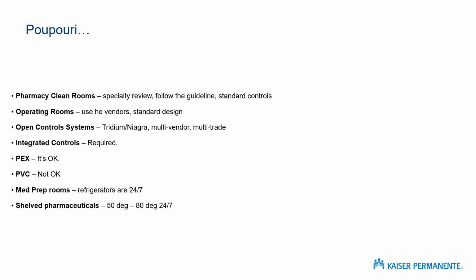Operating rooms, again, we have some standard vendors. We have memorandums of understanding with 2 vendors that provide operating room systems, and those operating room ceiling systems test out at ISO 6 and a certain microbial count. And so we have performance guarantees on the cleanliness of the room from those vendors. So use those vendors, use the standard design. Don't try to get smart and tell them how much CFM to use. Ask the vendors how much CFM do you need in order to meet your performance assurance, and then let the vendor design basically the system.